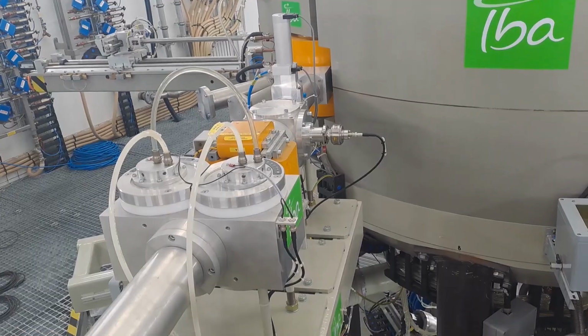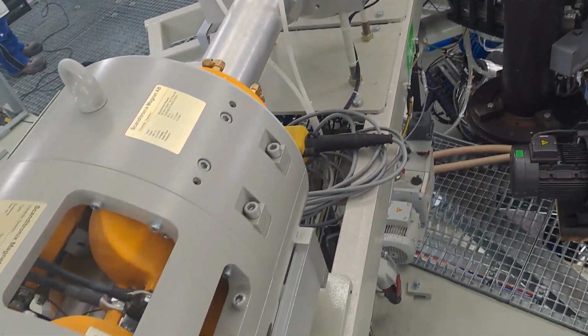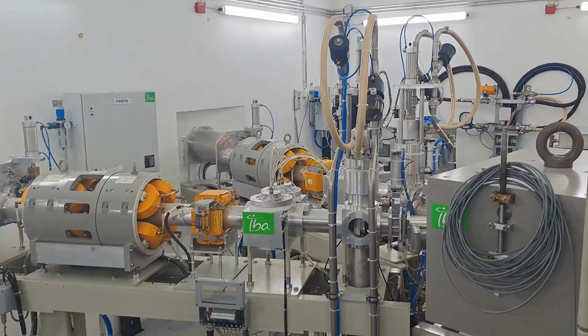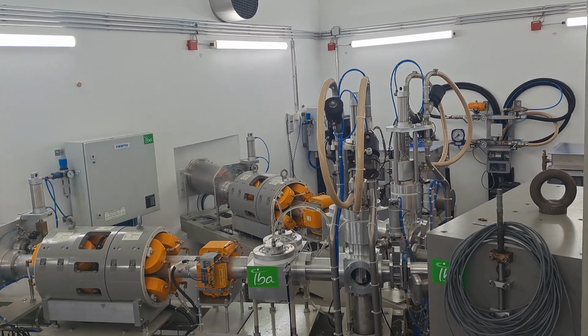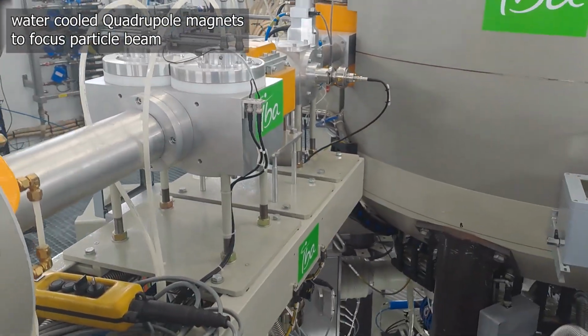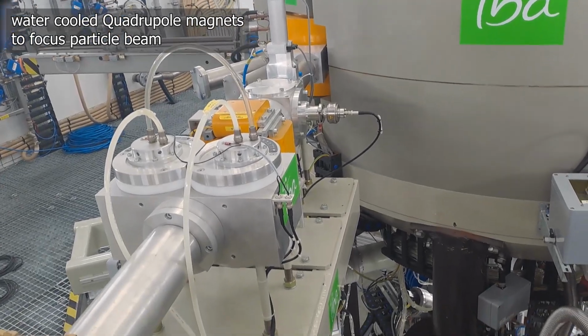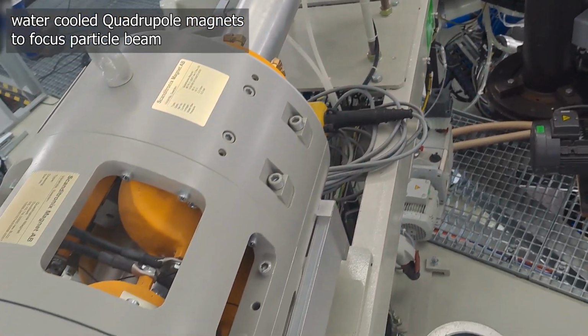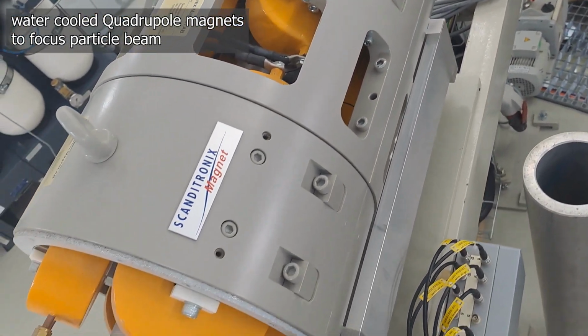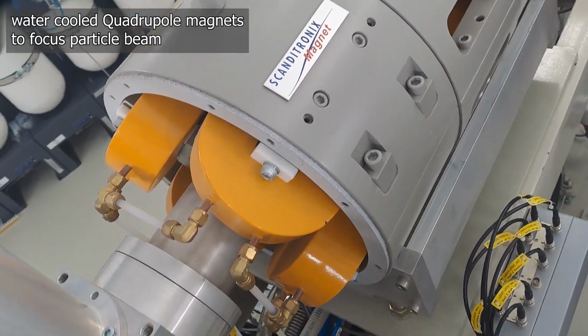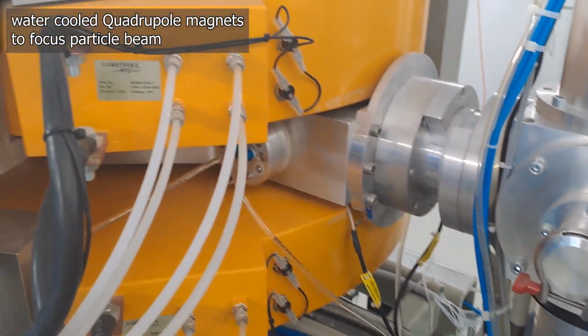On the respective line, only deuterons or protons can be used for the irradiation. Alphas are only used with solid targets, which we will look at shortly. These blocks here are quadrupole magnets, which are used to focus the beam. They have to be water-cooled. The bending magnets direct the projectiles to either the liquid or the gas targets.